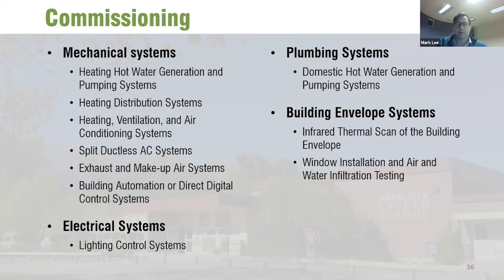Yeah, I think, Brad, the commissioning agent will oftentimes look at what has been selected for equipment. They won't necessarily propose new equipment, but what they will do is look at the equipment that has been selected by the design engineer of record, and they'll make recommendations for optimizing that. So for instance, if we have an energy recovery ventilator specified, they may look at it to say that if a particular manufacturer is specified, are there alternate manufacturers that make a more efficient unit? And so they sort of fine tune it at that level.